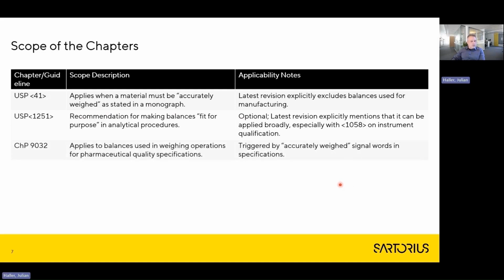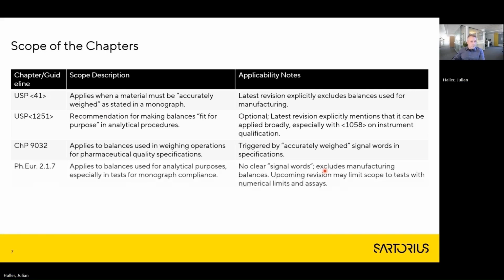The Guideline 9032 of the Chinese Pharmacopoeia applies to balances used in weighing operations for pharmaceutical quality specifications, and it is, like Chapter 41 of the USP, triggered by the signal words "accurately weighed." So whenever these words appear in a monograph, it is clear that the respective guideline has to be followed. The European Pharmacopoeia applies to all balances used for analytical purposes, especially in tests for monograph compliance. However, there are no such clear signal words. Manufacturing balances are explicitly excluded, and it should be noted that the upcoming revision may limit the scope to tests with numerical limits and assays.